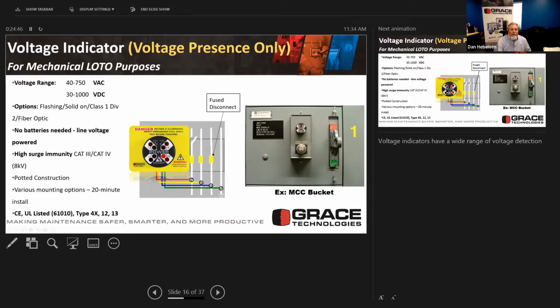But if we were to blow that fuse and we just dropped L1 out of the circuit, you'll see that voltage, as we measure phase to phase and phase to ground, is now starting to flash on the ground. So it's letting you know that there has been a loss of power on L1, and you can start to use this for some troubleshooting.